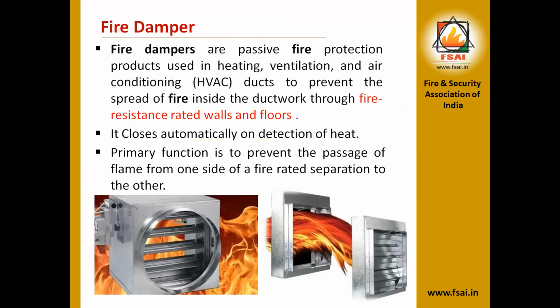The next is the fire damper. Fire dampers are passive fire protection products used in heating, ventilation and air conditioning, that is HVAC ducts, to prevent the spread of fire inside the ductwork through fire resistance rated walls and floors. This means that when there is a fire in the duct, the fire damper stops the fire from going out of this duct to another duct. It closes automatically on detection of heat, so there is no need to activate it. It is a totally automatic fire damper. As soon as it senses the heat or temperature, it closes itself. Its primary function is to prevent the passage of flame from one side of a fire rated separation to the other side.